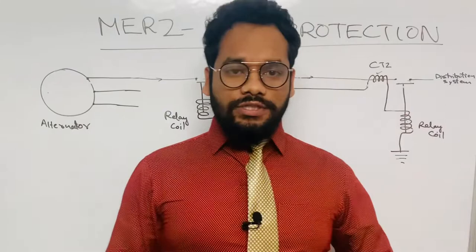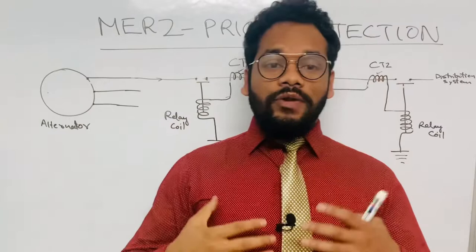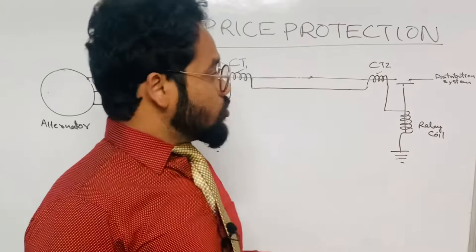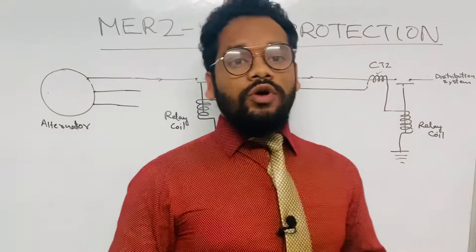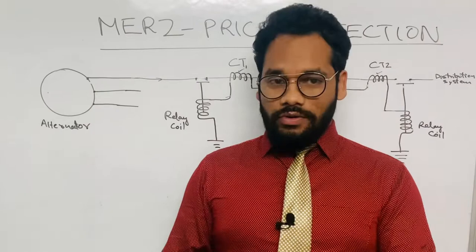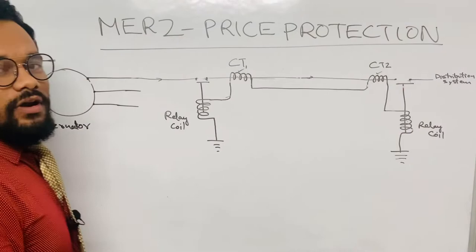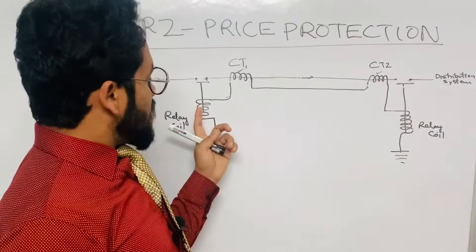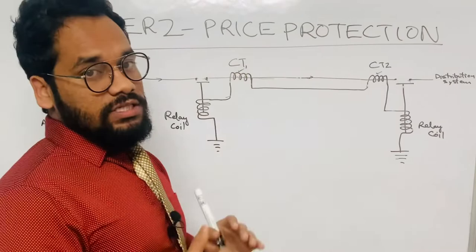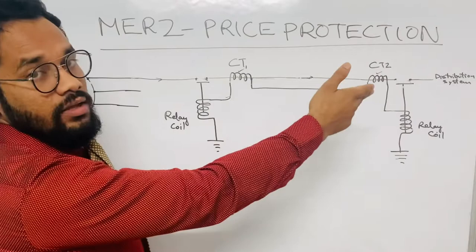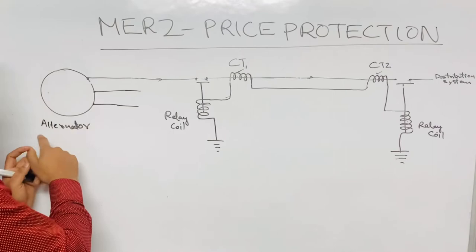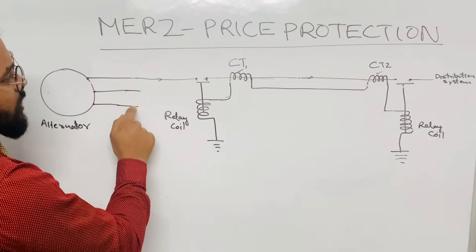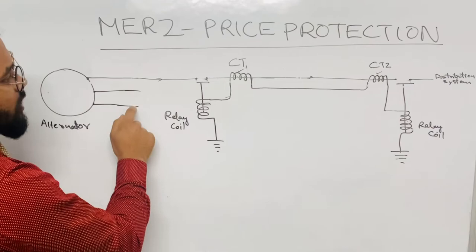To summarize: the Merz-Price protection system is a type of differential protection used in AC systems — specifically AC generating systems like alternators. It is not used in DC systems because current transformers cannot work in DC systems. It provides protection between phases and from phase to ground. The system employs two current transformers: one located near the source and the other at the entry point of the distribution system, interconnected by relay coils.